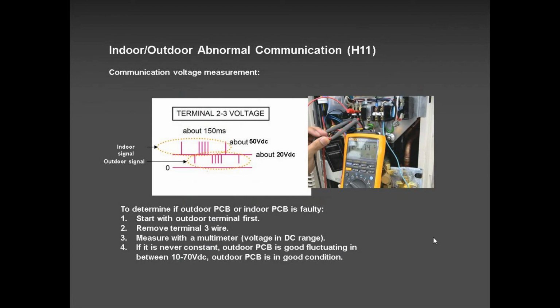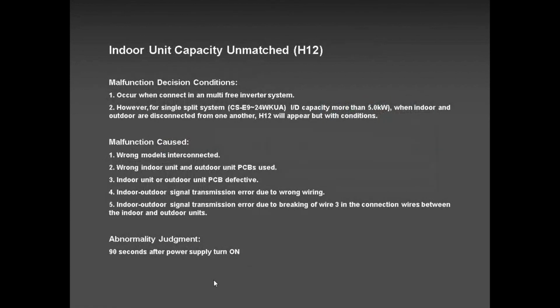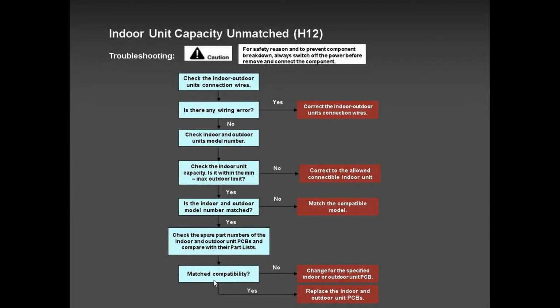And if you have this error code H11 down the road, let's say 3, 4 years down the road, 6, 7 years, I don't know, then you can always use the app to troubleshoot. And trust me, to troubleshoot whether it's the indoor or the outdoor PCB, it's very simple. Use this multimeter. Don't use an amp probe, because the amp probe might lie to you, especially when it fluctuates up and down, up and down. It might give you lower readings as compared to the multimeter. Use the multimeter, measure 2 and 3, the way it explains to you on the slide, or in our app.